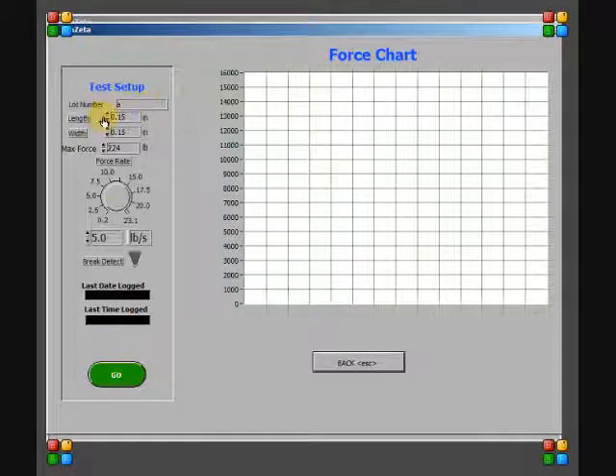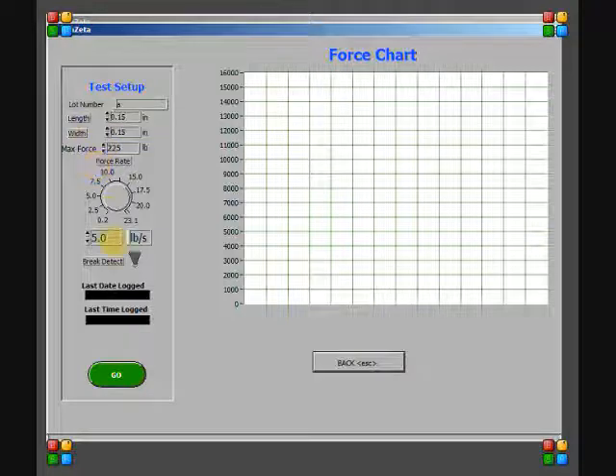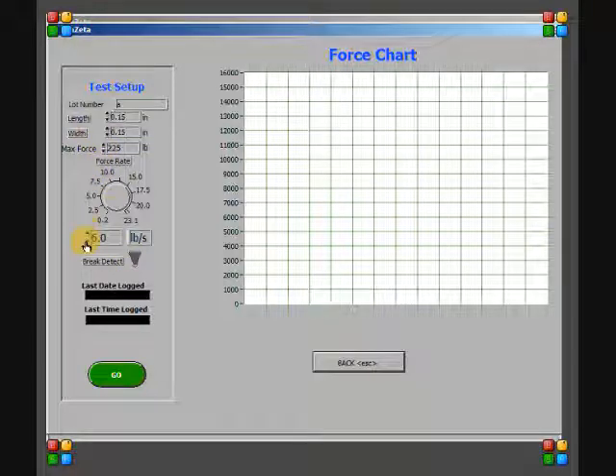The sample's lot number can be entered and the size of the sample, the max force, and force rate can be adjusted. The brake detect feature can also be turned on or off.